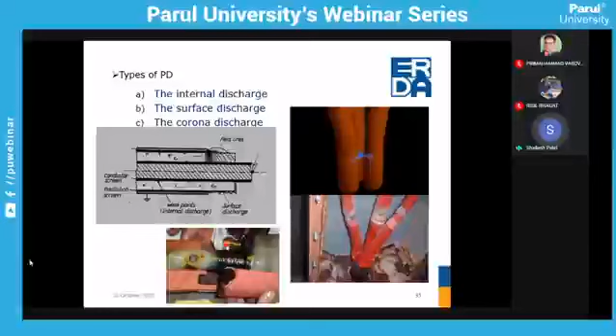This is nothing but due to high voltage puncture. It is not because of high currents. Failure of cables due to high voltage, in 90% of cases, is mainly because of poor terminations, or if any incipient partial discharge source is there in the cable, then failure will occur. This type of failure will be there in the field.